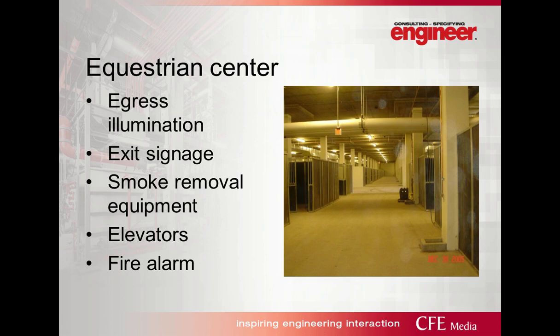Typically, if there's a horse in there, there's usually a horse handler in that space. So if I have 1,000 stalls in there, there's a very good possibility I'm going to have over 1,000 people in this building. So you can see an exit sign here. There's one at the end of that pathway, and that's obviously an egress path, needing 1 foot candle in the path. How do I calculate the foot candles in that path? If the floor is dark, I have to take those things into consideration because your reflectivity in the space also comes into play for maintaining that 1 foot candle average. My professional opinion is that you should always overlight a space for egress lighting.